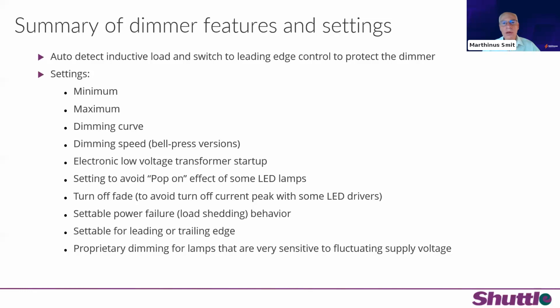So in order to solve the majority of problems that you encounter in the field, the ideal characteristics of a dimmer are that it must be able to auto-detect your inductive loads. You must be able to set your minimum and maximum intensity. You must be able to set your dimming curve and your dimming speed, especially if you use a bell press dimmer. It must have a setting to start up your electronic low voltage transformers. For that pop-on effect of some LEDs at low intensity, you must have a setting to address that. If the dimmer has a soft turn off, that fade off effect, you must be able to turn that off and provide a sharp turn off to avoid that current peak in some of the drivers, as we discussed earlier.